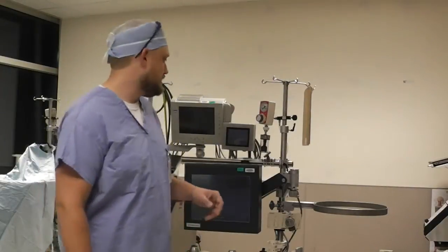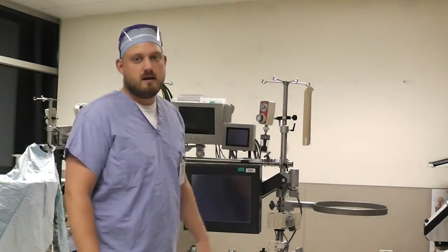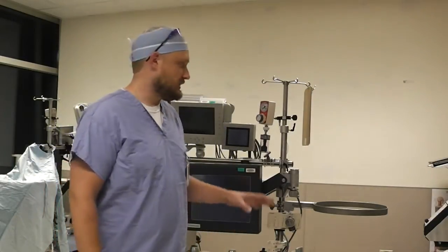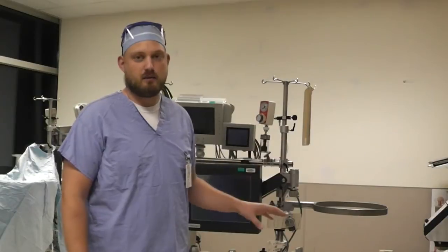So normally when you come into the room, there will be a pump already set up, and you're going to immediately start priming that, and after you're done priming, you're going to build a backup to put your pump back together after your case. As you're probably already aware though, you will be asked to do a priming exam in which you will be timed. And in that exam, you will actually start with a bare pump, such as the one that I have here, and you will come in, build a backup in the morning. That will not be part of the timed portion. But then you will set up the pump and prime it as part of your priming exam.